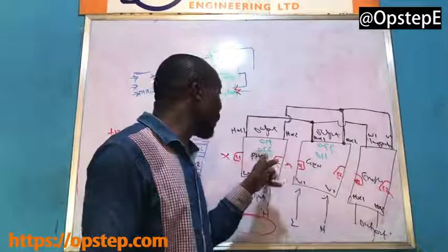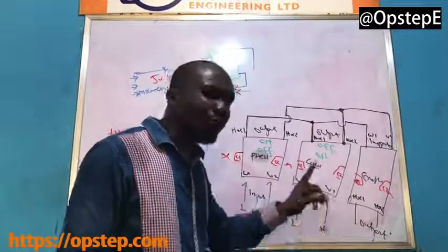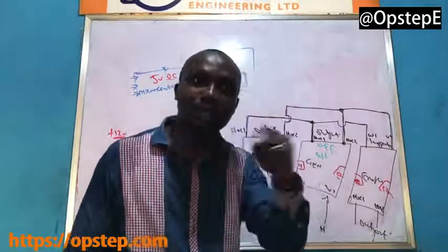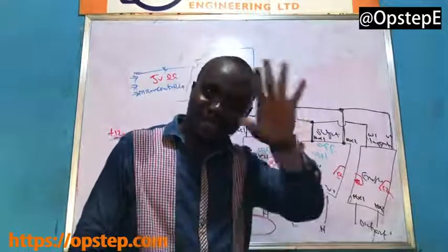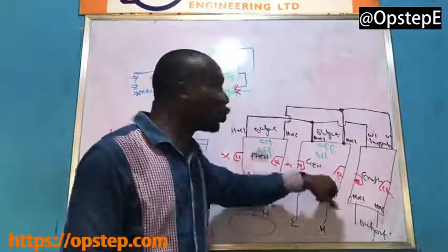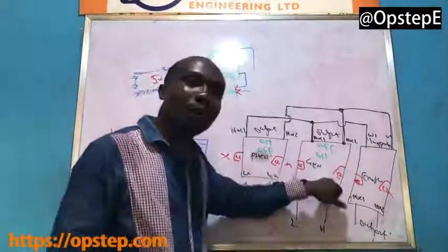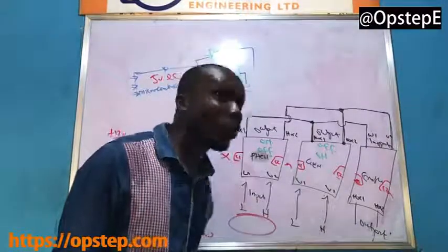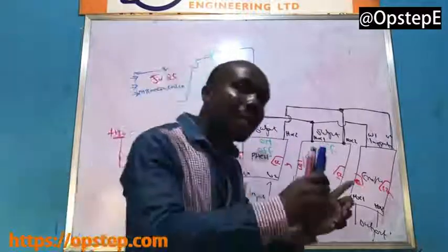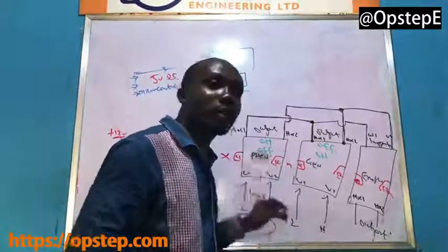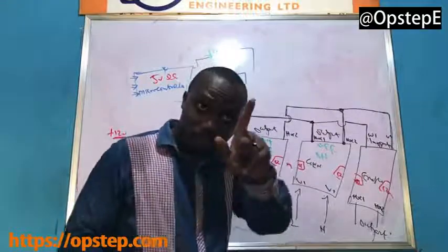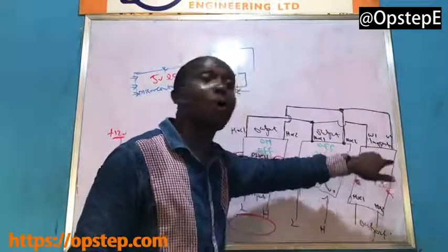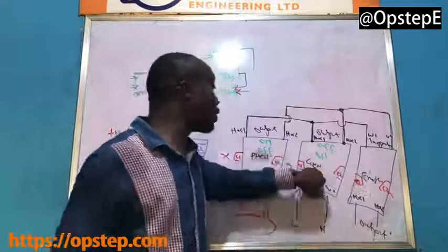Or to generator. Don't forget, in manual mode, it does not have priority. Who is the priority? You are the priority. Whatever you ask it to do or state is priority for it. So it's okay, switch to generator. The moment you tell it to switch to generator, it automatically does what? Switches off this one for you. Not switch off the generator, not switch off NEPA. It only disconnects this coil so that it is not supplied to the house. And it has turned this one off too.